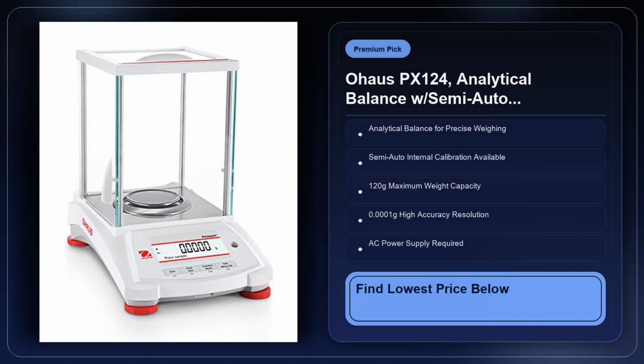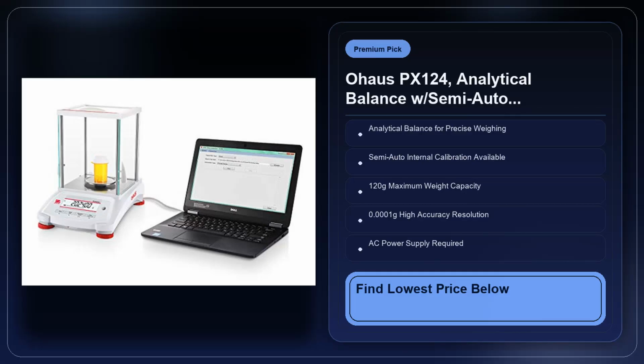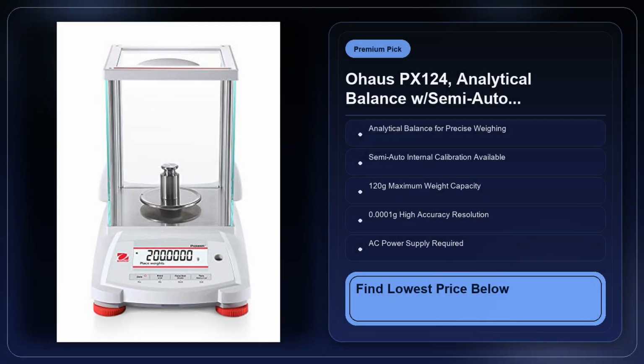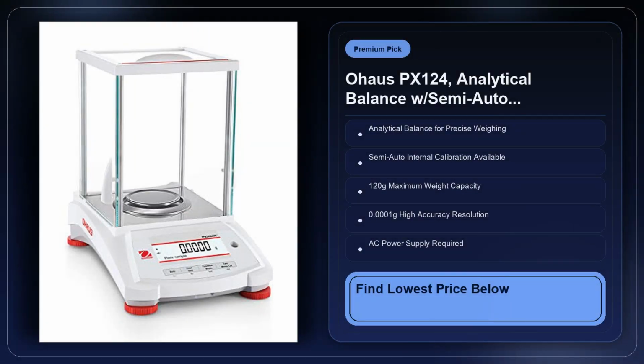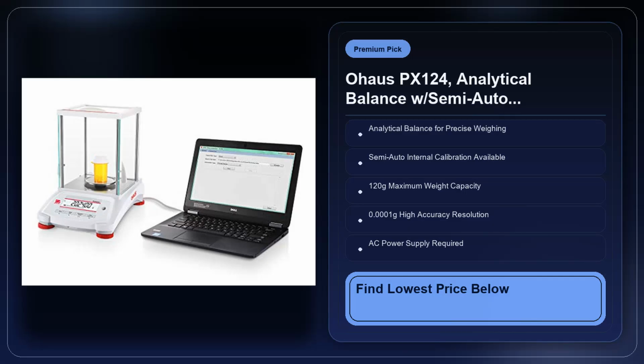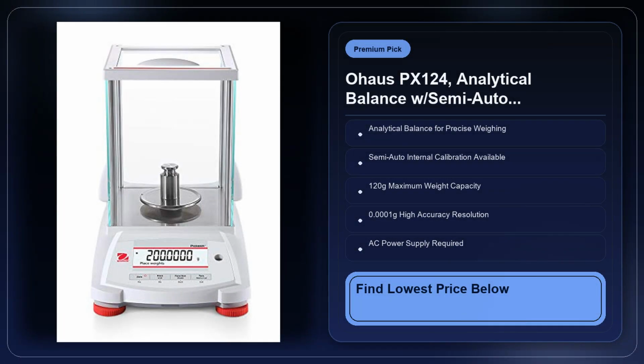Now, let's talk about the practical trade-offs. The 120 g capacity might feel limiting if you're working with larger samples, such as bulk reagents for a university chemistry department. You'll need to split a larger batch into multiple weighings, which adds steps to the workflow. Also, the balance runs on AC power only, there's no battery backup. If you're in a setting where power interruptions are common, you'll need to plan for a UPS or accept that the balance will shut down and you'll have to recalibrate once power returns.